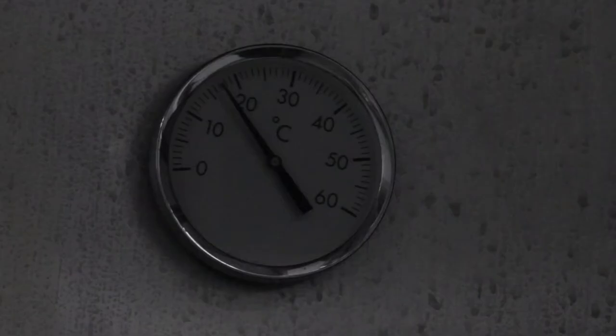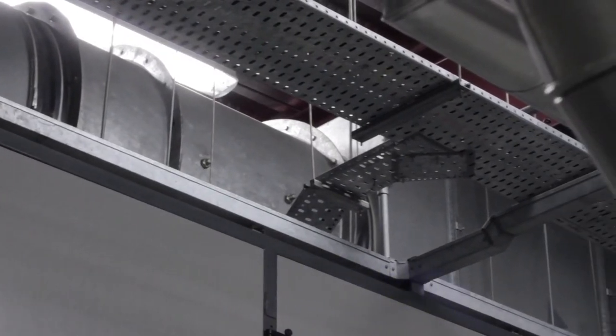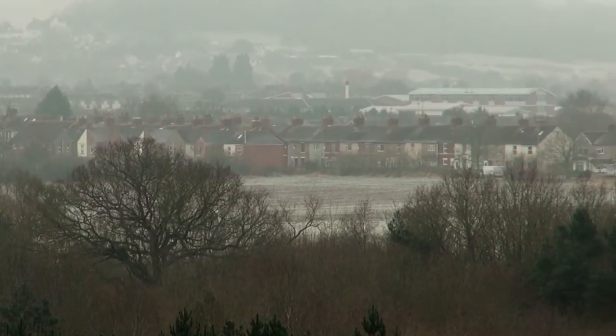Any building with a lot of IT equipment in, we find that overnight the building gets warm. And what we did with the building management system is we use natural fresh air. So depending on the outside temperature, at 5 o'clock in the morning, it actually sucks in fresh air, which is cooled, and it circulates that throughout the building. So when you come into work at 7:30, 8 o'clock, it's as if somebody's had the air conditioning on, the building's at a nice ambient temperature.